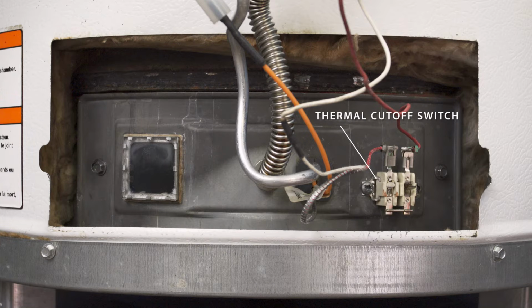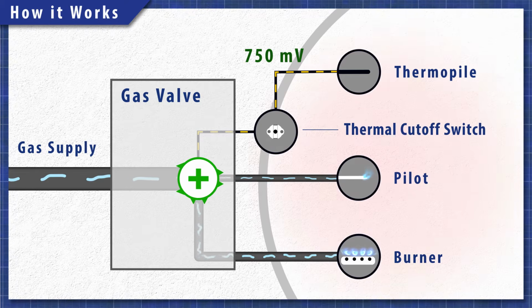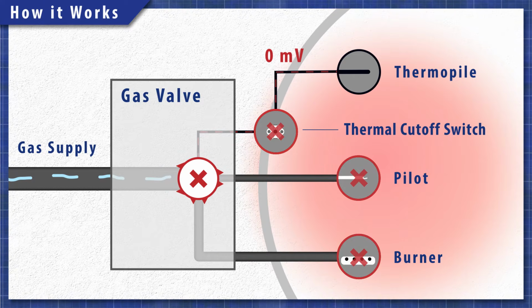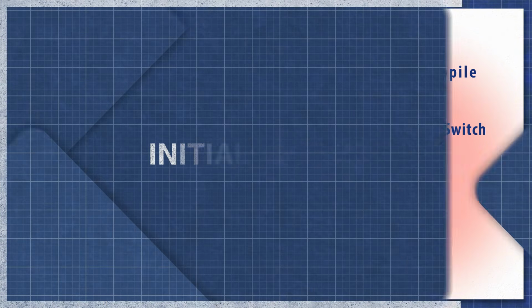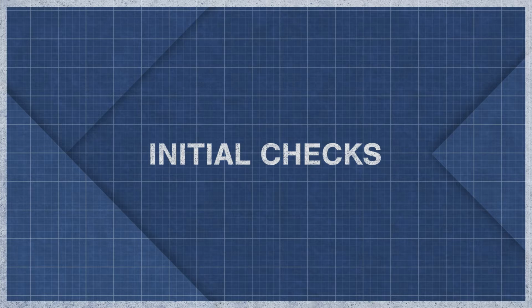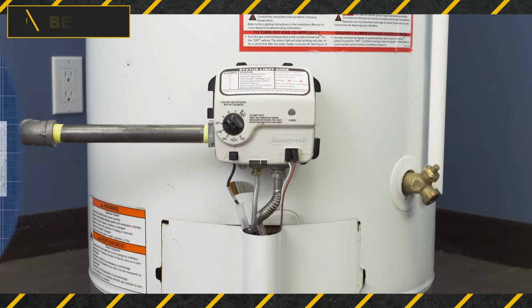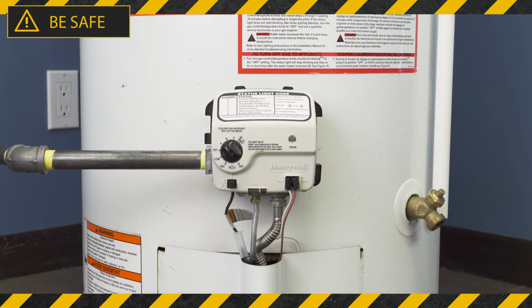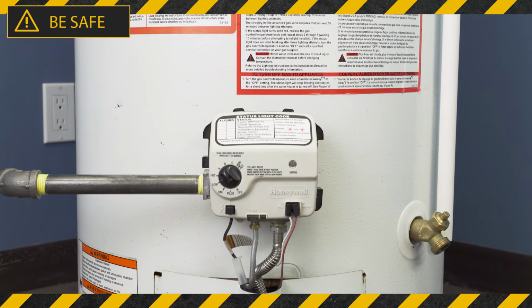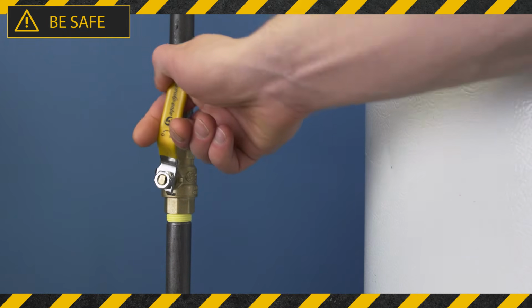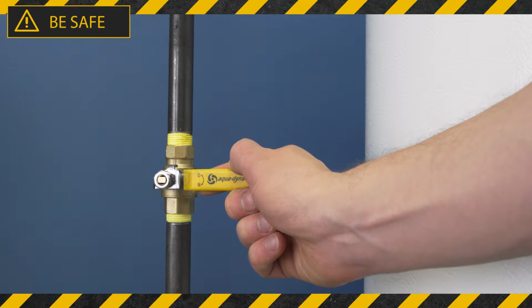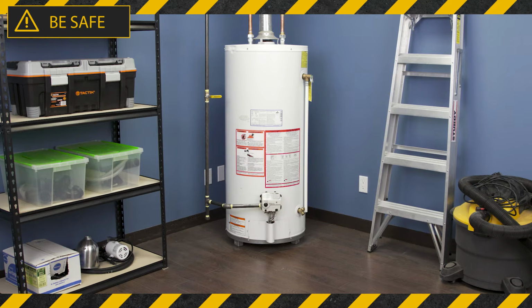Additionally, the TCO, or thermal cutoff switch, is wired in series with the thermopile. If the temperature in the combustion chamber gets too high, then the switch will trip and cut power to the valve. Always be smart when working with gas. If you notice a strong gas odor at any point, then shut off the gas, ventilate the area, and immediately call a technician.